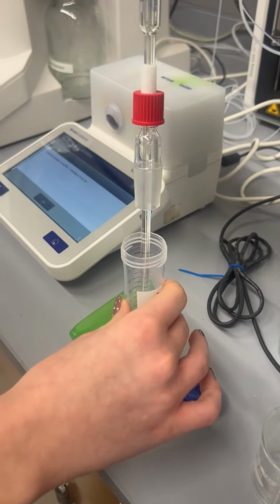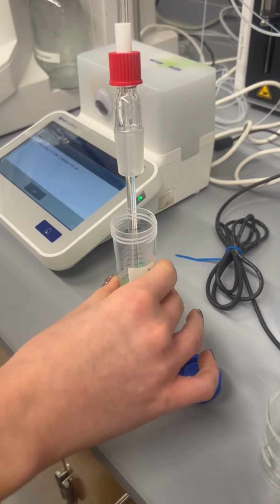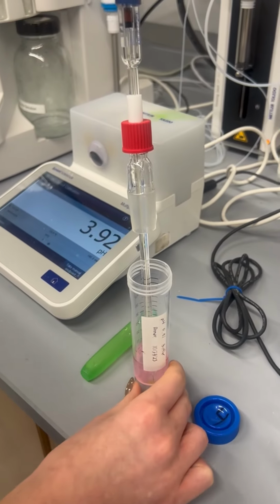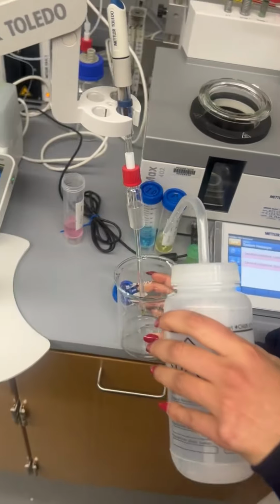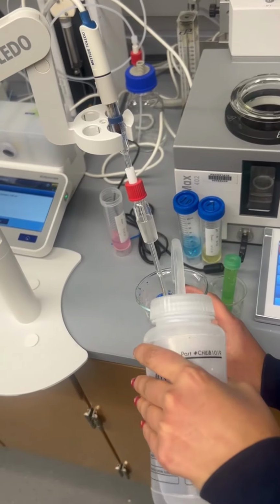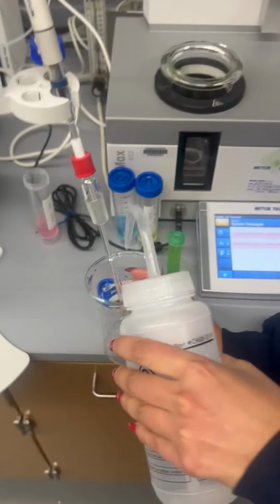Once you've done that, you're going to click OK, and then you're going to wait for the pH sample to calibrate. Once it's done that, you'll hear a beep. Then you're going to clean the probe and repeat the process for pH levels 7 and 10.